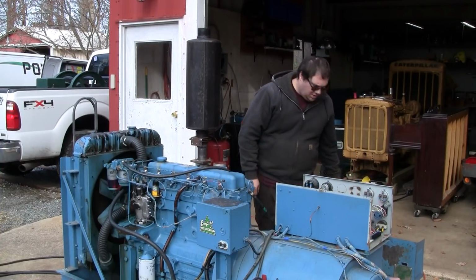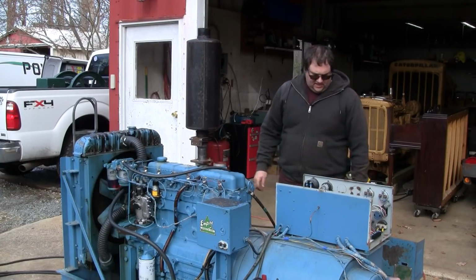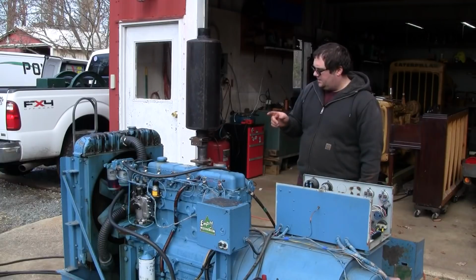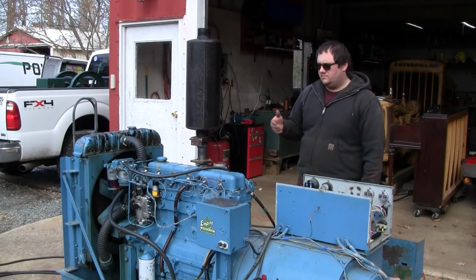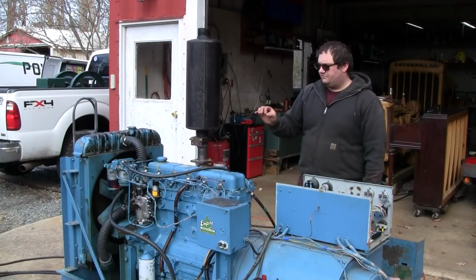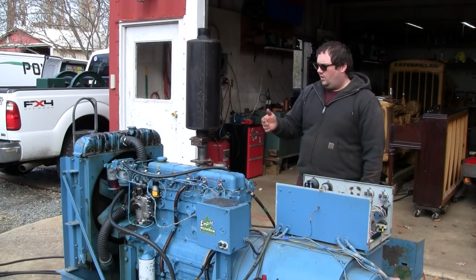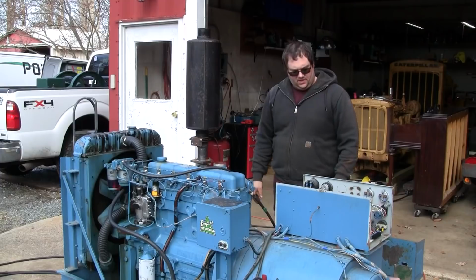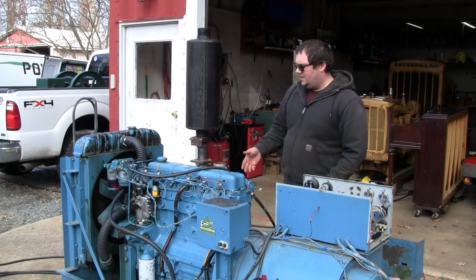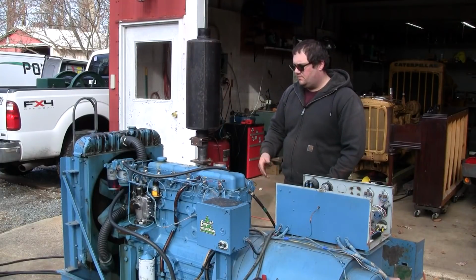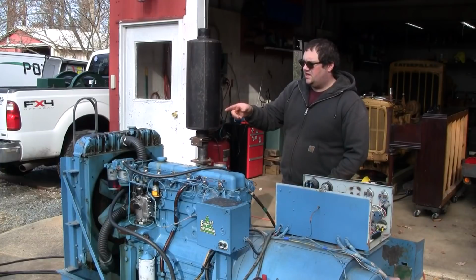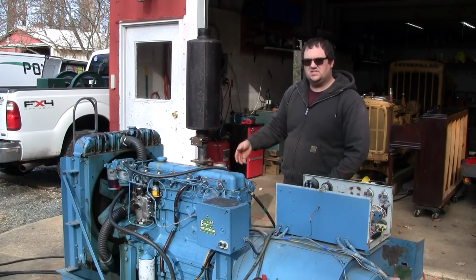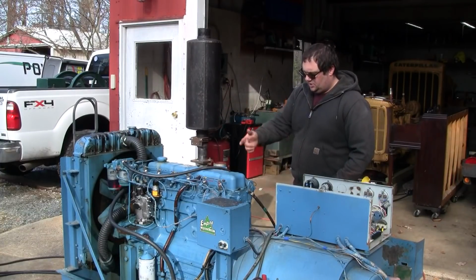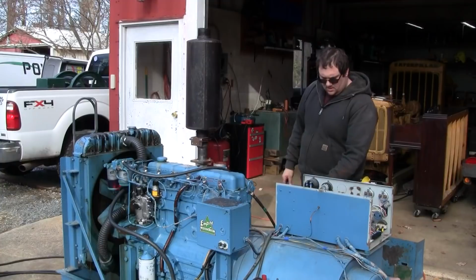I've got my plank of wood over here in case I need to choke the engine out. It might not run at rated speed since we had the whole thing apart, so we'll have to fine-tune the running speed once it's actually running up to temperature. I'm just going to start it wherever it's running, as long as the starter disengages I'll be happy. I have the load bank energized so I can look at the frequency and get an idea of the engine speed. All the injector lines are tight. Let's start it up.